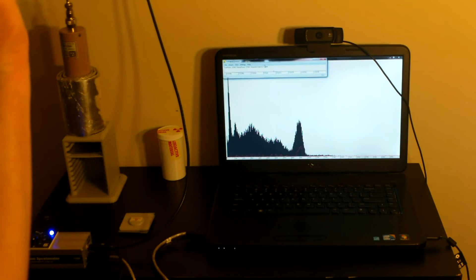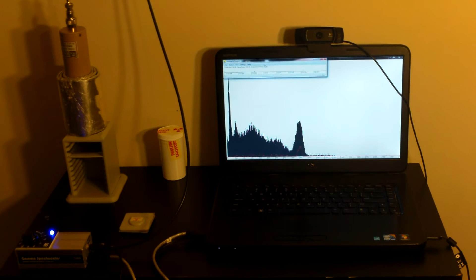And when barium-137M jumps down to barium-137, that difference, that surplus energy, shoots off as a gamma ray at 661.66 kiloelectron volts. That's that right there. And there's a bunch of little X-rays that are emitted too, K-alpha-1 and K-alpha-2 X-rays. They go flying all over the place, and you see those down there. So anyway, let's calibrate the unit, get it all set up, and take a look at cesium-137.